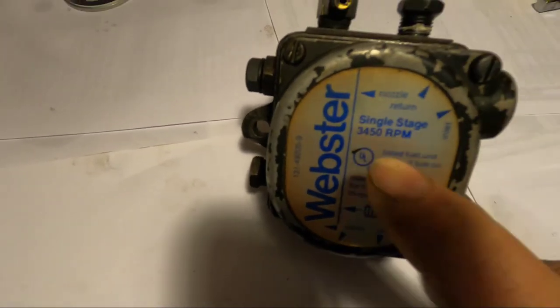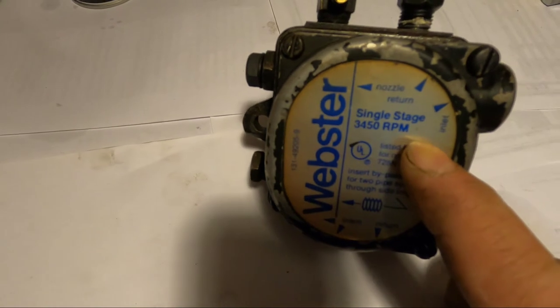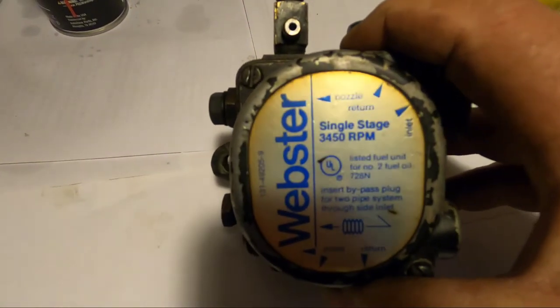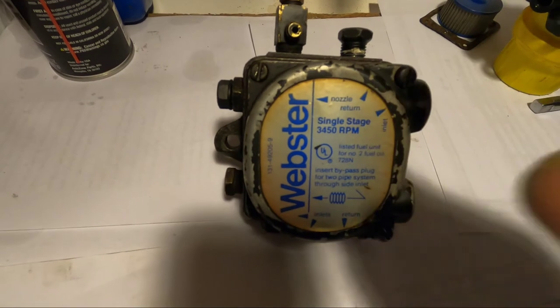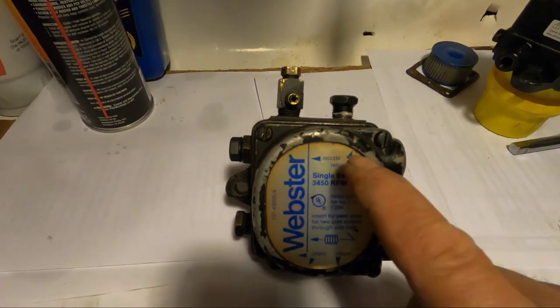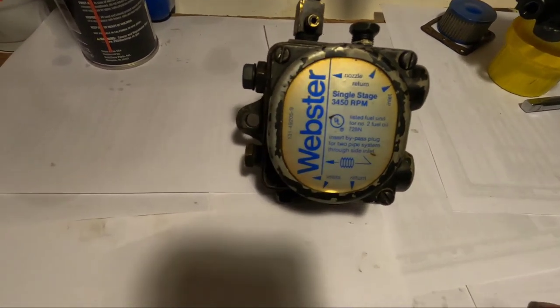Now, I'm pointing this out because this fuel pump is anywhere between 20 to 22 years old. It's the original pump that came with the boiler, and the boiler motor burnt out a couple times, but not the pump. Anyway, about a week ago, this pump stopped working. We had cold weather and the boiler just wouldn't turn on.